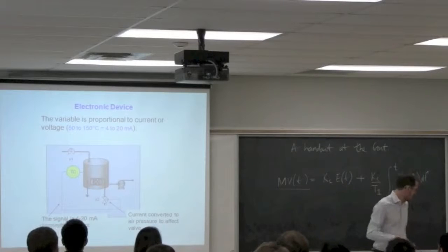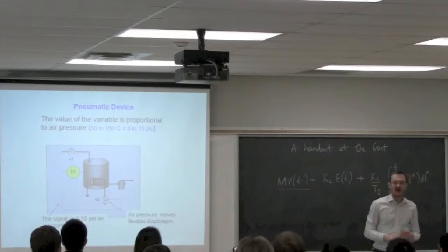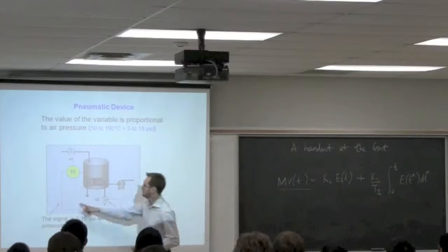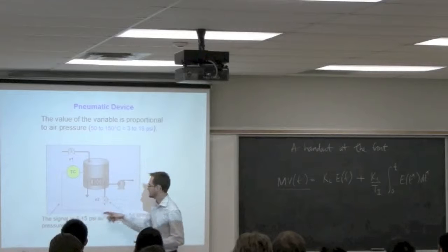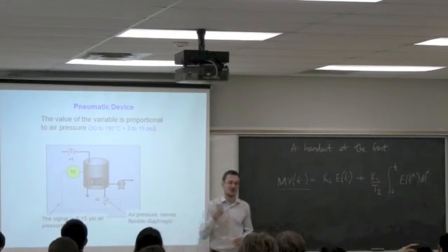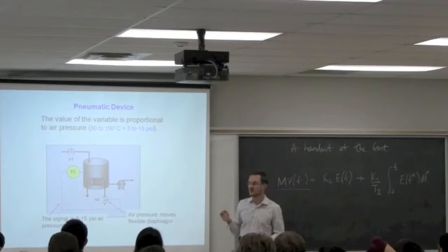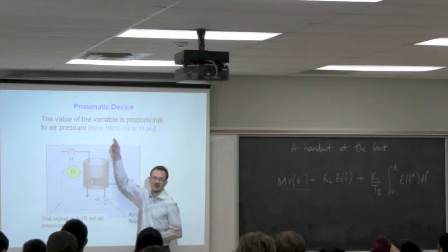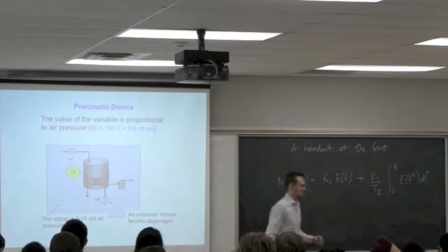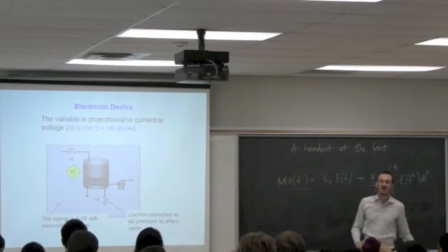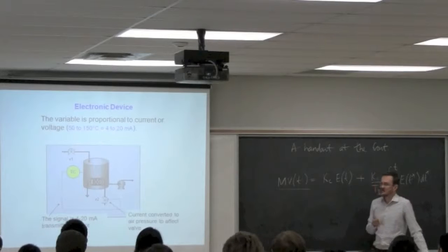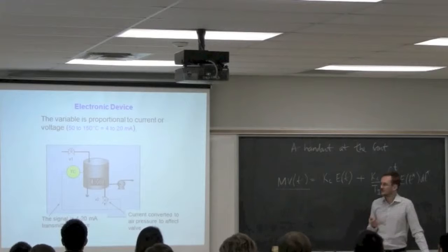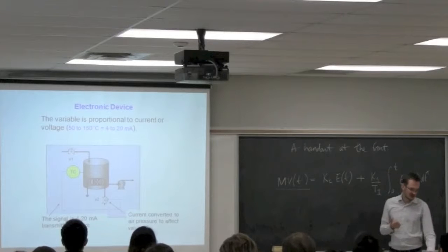Pressure signals, we're obviously limited by elbows, and we get pressure losses. So every bend you have in this piping, you get a pressure loss. And a pressure loss here actually has a problem. If you have a pressure loss in this pipe, in other words, you're sending the wrong signal. Electrical signals don't get degraded by that. Electrical signals can go hundreds and hundreds of kilometers without degradation. So we prefer electrical signals.